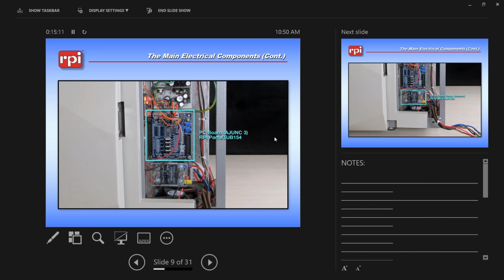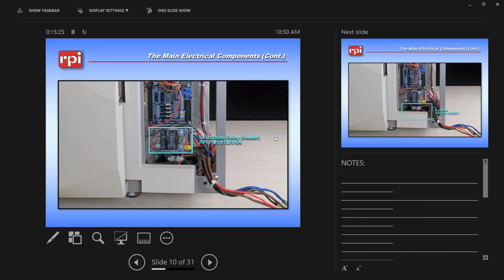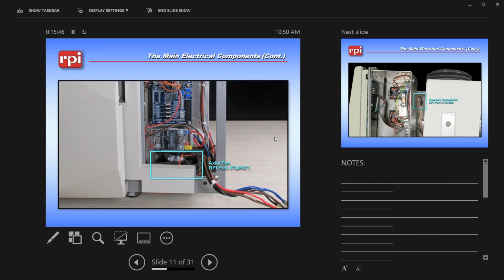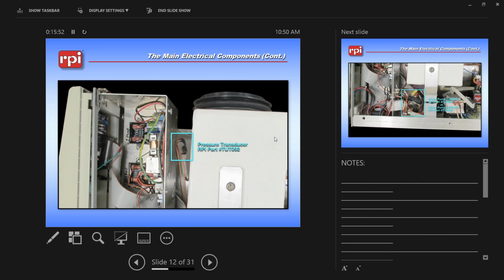Then of course we get to the adjunct board, which is responsible as sort of an input-output board for these units. This is what you'll be calibrating anytime that you go in to do a calibration. The solid state relay for the heater. This is again an electronic trigger to allow your heaters to turn on. It is the only one that has the white plastic casing over the front of it. So that's how you identify it from the other two. And then of course your cooling fan or axial fan. This is just to cool off the electronics. Right behind the electronics housing, you'll see your pressure transducer, and of course this is responsible for recording any pressure that the unit has.